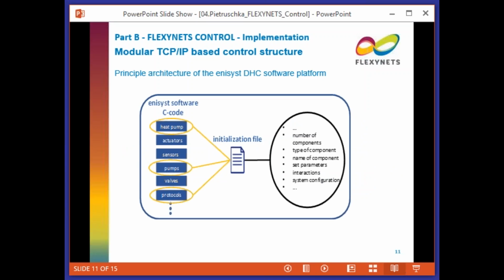How is this control system structured? The control code is more or less C code in each controller, and we operate with the same code across controllers. This code has different levels for different types of applications and systems integrated into the control. We have an initialization file which decides which components are actually available at each control substation, and only these are activated and combined into a control system. It's quite modular, so we remain flexible in motivating and adapting it to different possible substation situations.